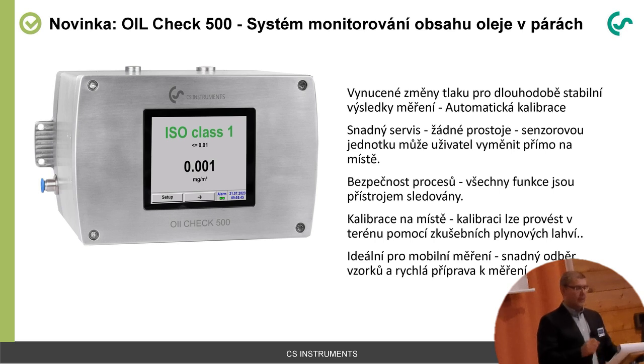The new OilCheck has an automatic auto calibration, which is called the force pressure variation. This helps us to have a long-term stable measurement. Then it is quite service friendly because we have no downtime. The sensor unit can be replaced by the user on site. There is no need to send back the OilCheck 500 for recalibration. Then we have good process safety, so all functions are monitored internally. It is possible to have an on-site calibration when using test gas cylinders, and it also could be used for mobile measurement.